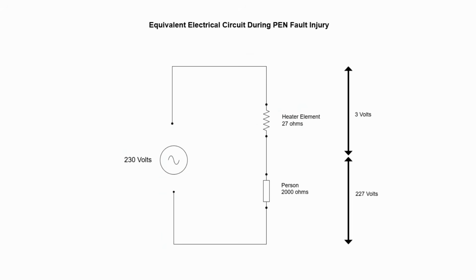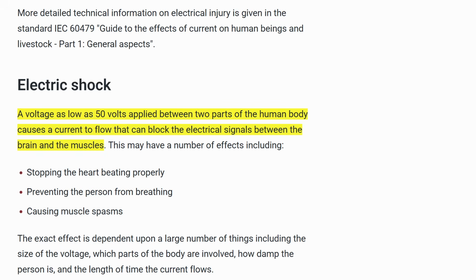This circuit can be simplified as a 27 ohm resistor, which is what the resistance of a 2 kilowatt heater element would be, and our person, who might be a few thousand ohms. The voltage of the supply is split across the two in the ratio of the resistances, and so the person gets the majority of the supply voltage across them, about 227 volts in fact, which is well above the 50 volts AC considered potentially dangerous.